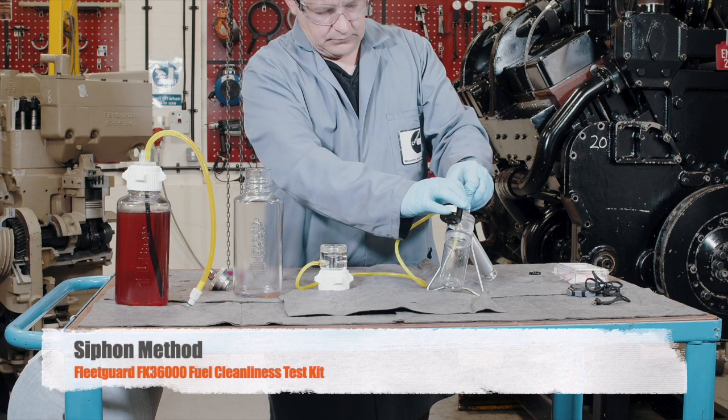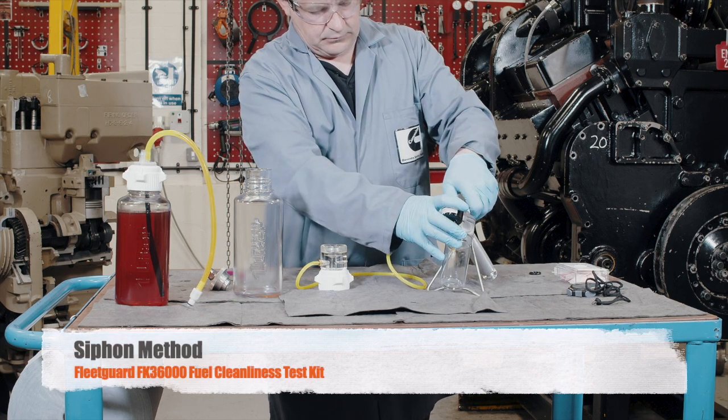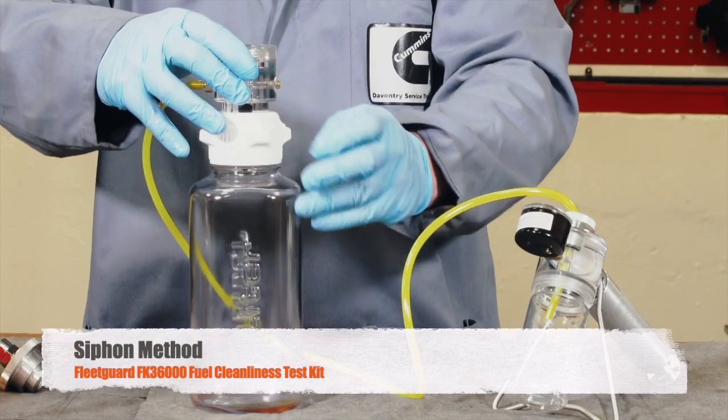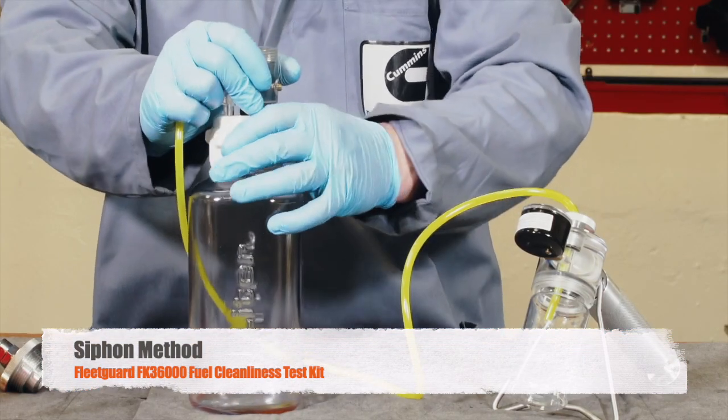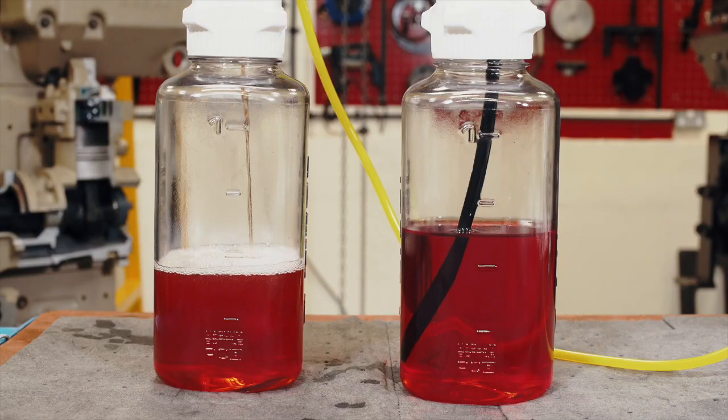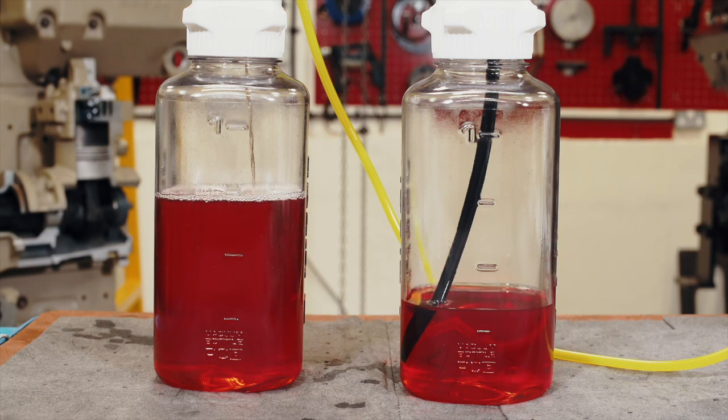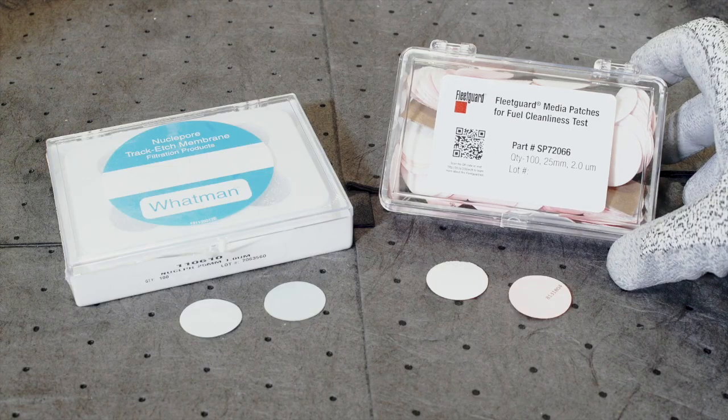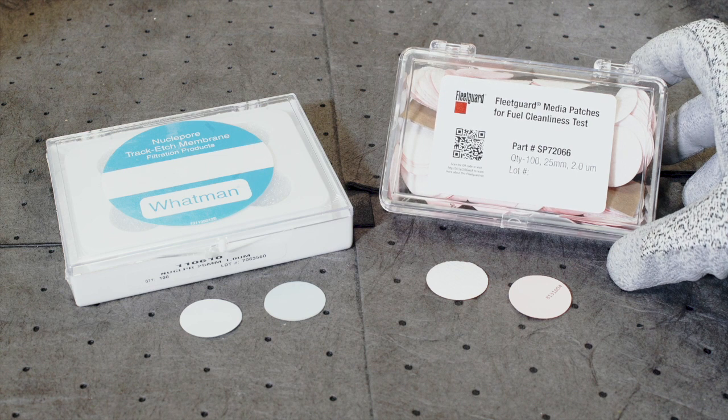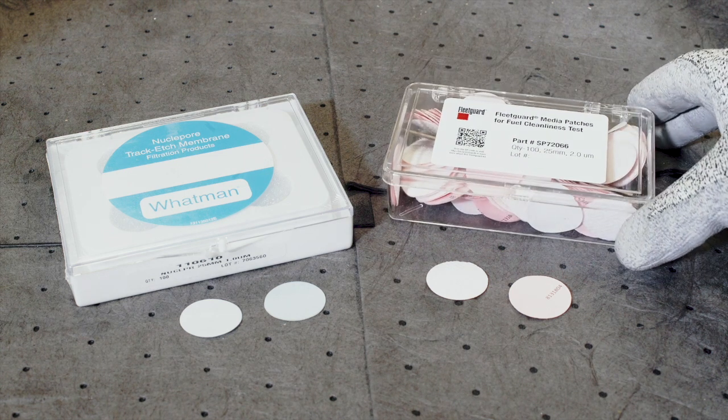Start by assembling the equipment in accordance with the instructions provided, ensuring that the vacuum hose is securely fitted onto the vacuum adapter and that the aluminium collar on the vacuum pump is tight. The siphon test method times the flow of one litre of fuel through the filter media. This test is only suitable with the two micron media; you cannot use the one micron membrane for the siphon test.